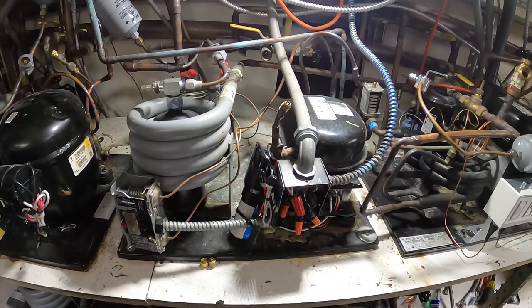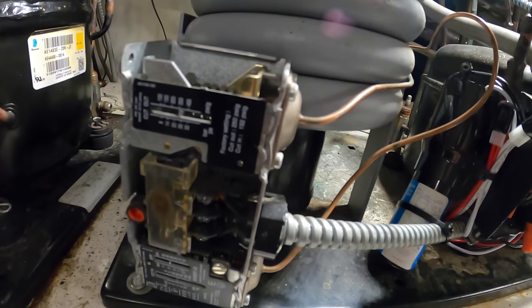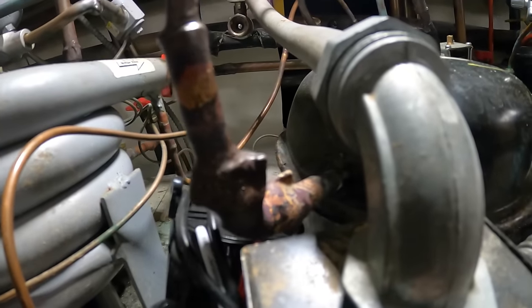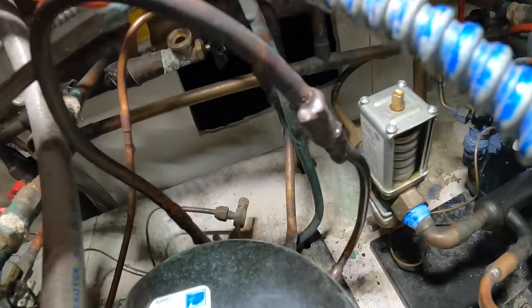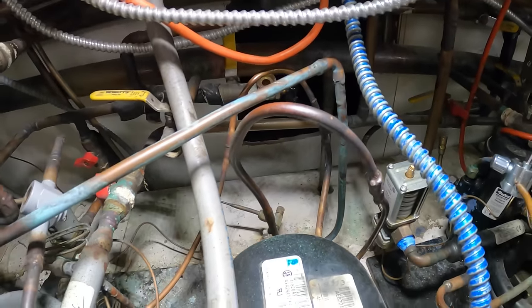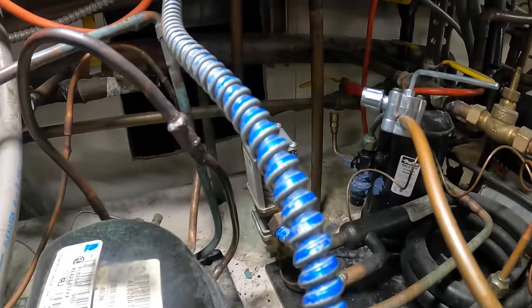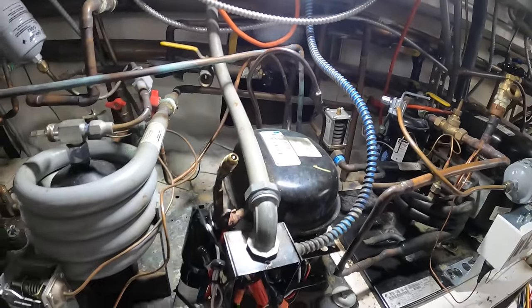We found this system with a large leak in it, and not only that we have a few leaks down here and it's just time to change this thing. We've got missing covers, wires exposed, and this compressor was already on its last legs with this hard start kit. Look at this connection — just using random pipe sizes to make this thing work to gain pressure. I mean this thing is as bad as it gets. Down there in the corner we have rusted service valves, and if you look here we have leak lock which would most likely contaminate the system. There's blue stuff on here — they're trying to stop leaks. It's just honestly a complete mess.